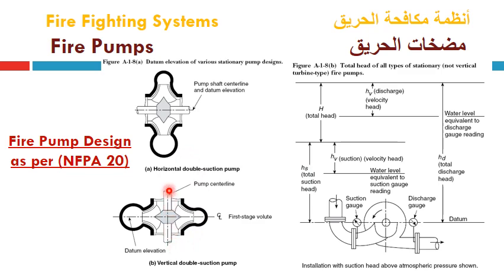Also here, in this vertical shaft, the impeller is affixed on the shaft, and it is supported by two bearings, one on the base here and one on the top. The flow from the suction flange is divided between both eyes of the impeller, from this side and from this side, half of the Q from here and the other half from here. Due to the rotational motion of the shaft in the vertical direction, the impeller will rotate and collect the water in this volute casing until it reaches its maximum diameter at the discharge flange at the outlet of the pump.